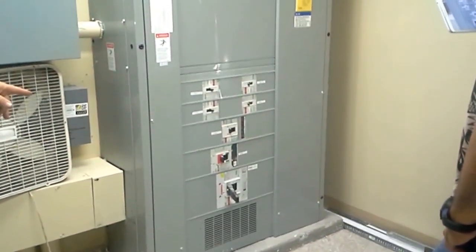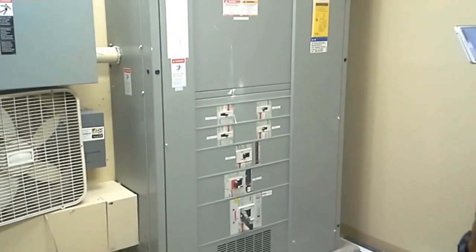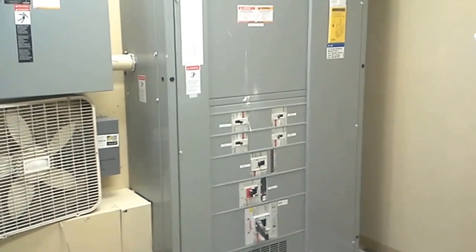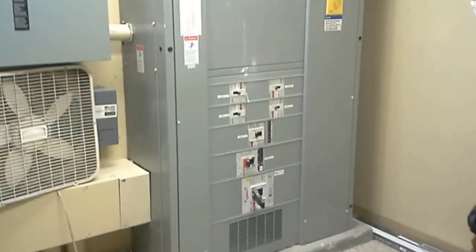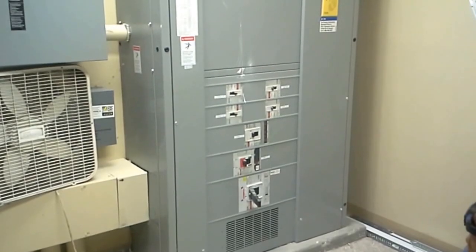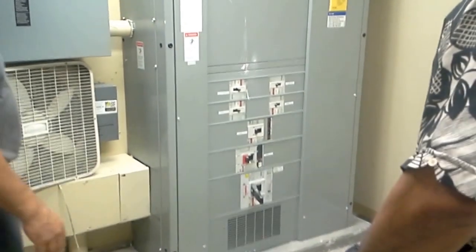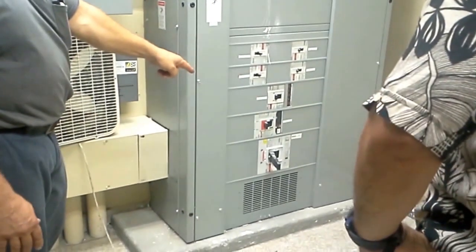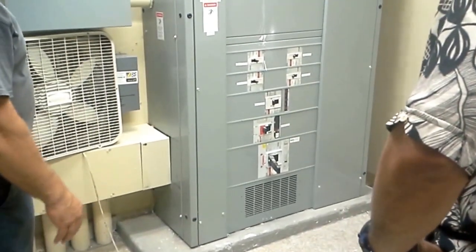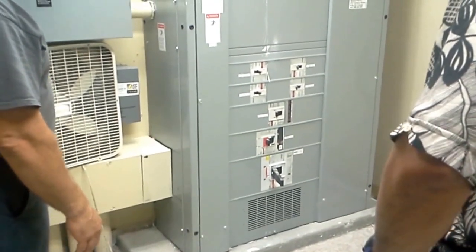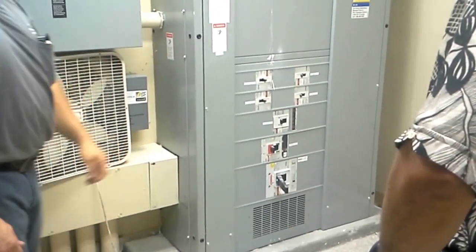And that'll trip. A lot of times you have a close lightning strike or something like that, something short of that circuit. So it's supposed to trip. So it trips, starts the generator, carries your load, and will never come back until I have utility or S1 available, and it won't come back until that has been retripped.